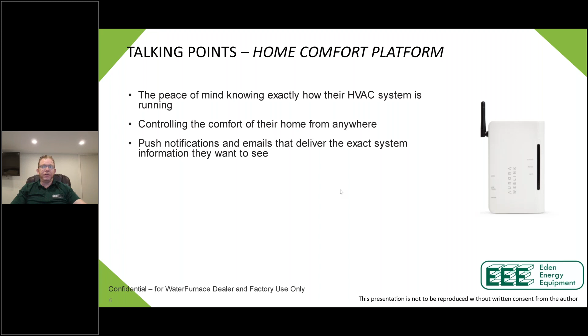It also sends out push notifications, by email and also by text. I'll caution you, if you use the text function, double check the phone number you put in, because we don't have a way to validate it. It's only happened once, but I got a call from somebody out of the blue saying their Symphony kept sending them notifications — turns out it was just 'a Symphony' sending text notifications to the wrong number. So as a contractor putting in the phone number, make sure it's correct. That's really the only technical issue we've had with Symphony, which is quite impressive.